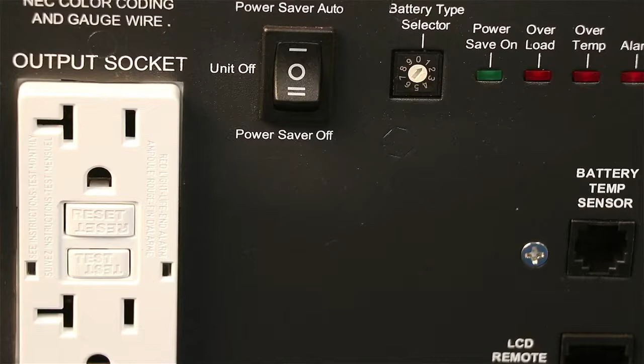Now when you put the switch in this position, power saver auto mode, in order to save power, when the unit is in DC mode—just connected to the battery with no AC connections drawing power—the inverter doesn't turn on. But when you turn something on drawing more than 25 watts, it senses power being drawn and turns the inverter on, giving you 120 volts for your accessories.